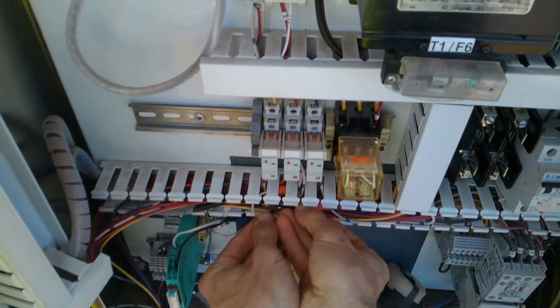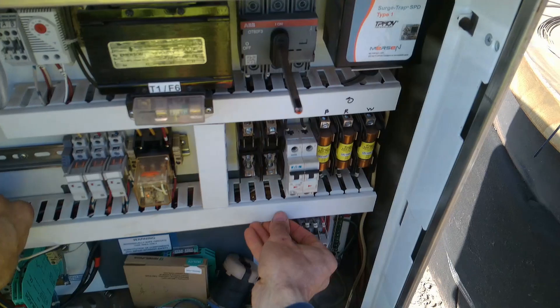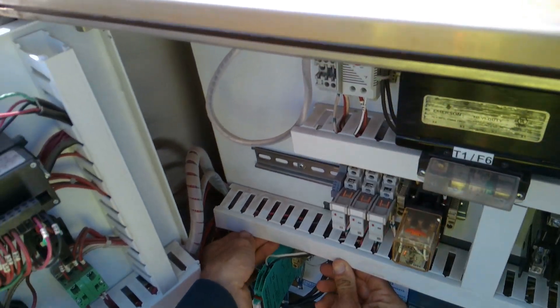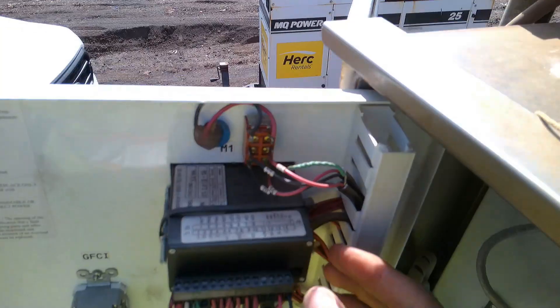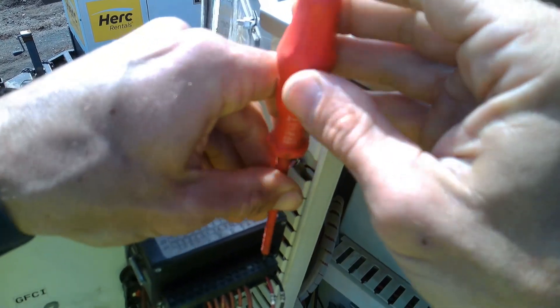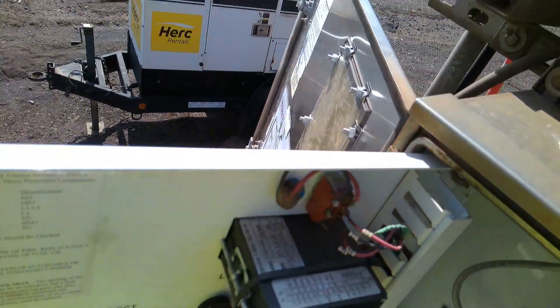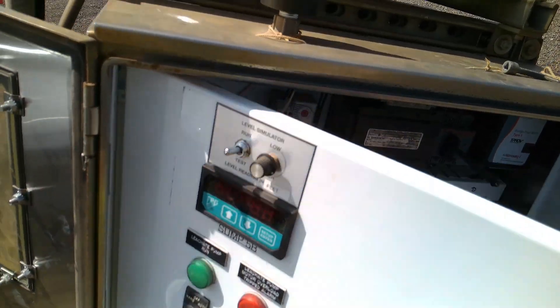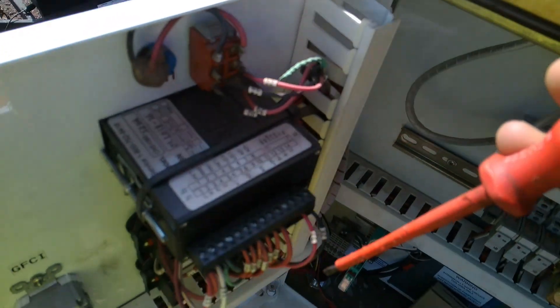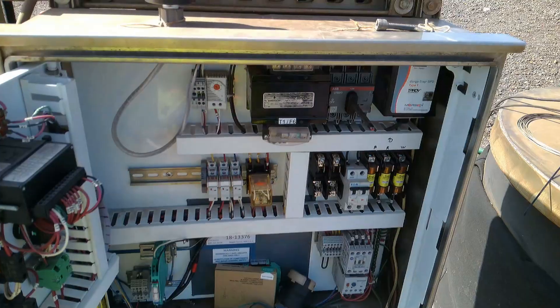Let's put this cover back on. And then the last step is terminals 27 and 28 to our little display controller. This thing takes an analog input, has a little display that shows the analog input, and then has relay outputs that you can program on the screen. It's by EPG Companies — pretty good little model, does its job. Those are good too. And we have a shield there — let's tighten that shield up. Very good. Okay, that's all the connections.